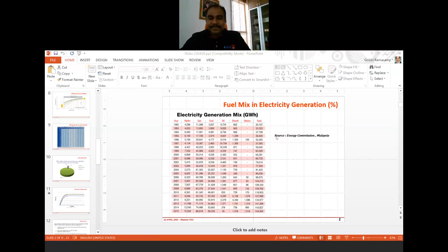Next question is from Chan. How should we decide whether a variable speed drive should be used for a motor for energy efficiency? Okay, if you have a motor system with clearly variable load, for example the pump system that I showed you, where you are using a mechanical valve to control the flow, that's a good example where you should replace it with a variable frequency drive. Or you have a fan system where you control airflow with a damper. Some kind of variable load system where you are currently achieving the variable load by using a mechanical system, valve, damper, and so on, should be revisited and considered for a variable frequency drive.